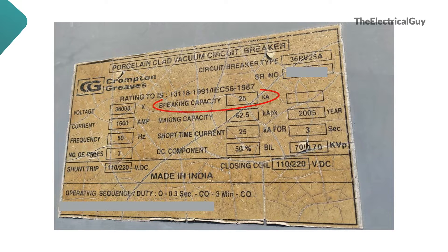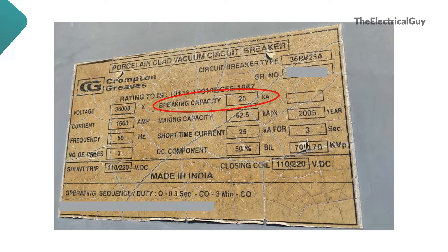Next is breaking capacity — it is the highest RMS value of short-circuit current which the circuit breaker is capable of breaking. This is also called rated short-circuit current or symmetrical breaking current. This breaker is capable of breaking 25 kA.